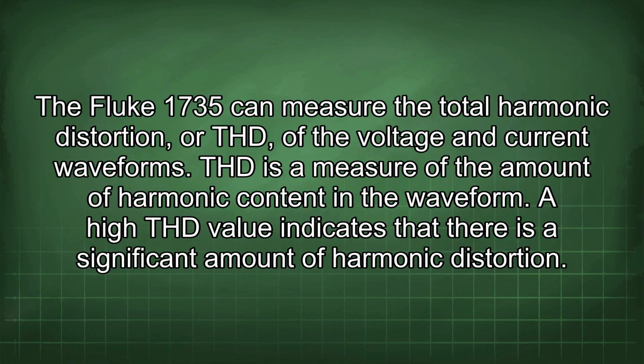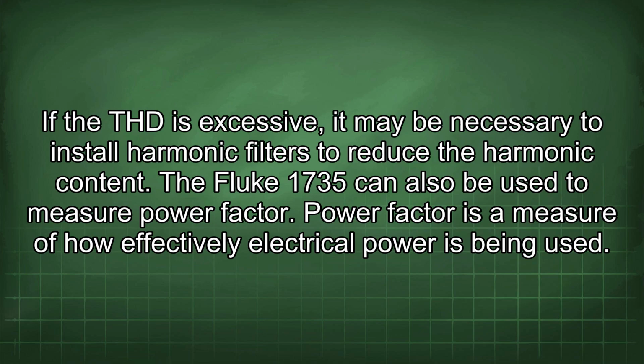The Fluke 1735 can measure the total harmonic distortion, or THD, of the voltage and current waveforms. THD is a measure of the amount of harmonic content in the waveform. A high THD value indicates that there is a significant amount of harmonic distortion. If the THD is excessive, it may be necessary to install harmonic filters to reduce the harmonic content.